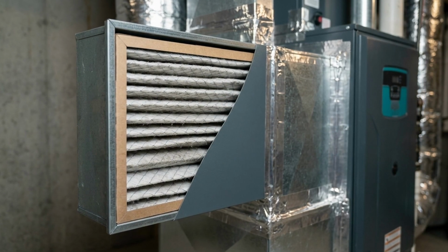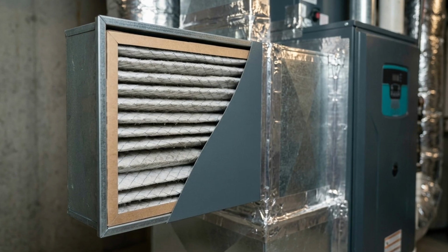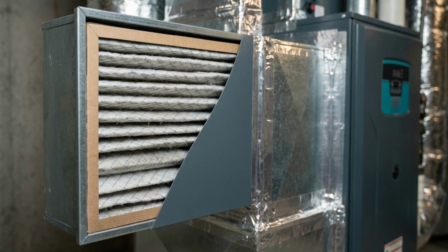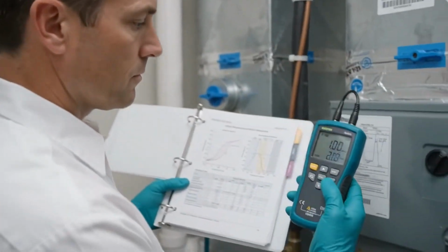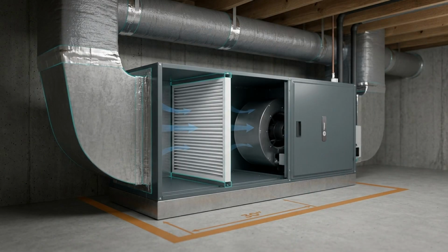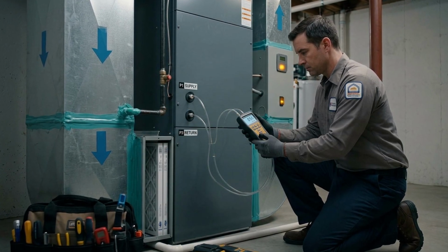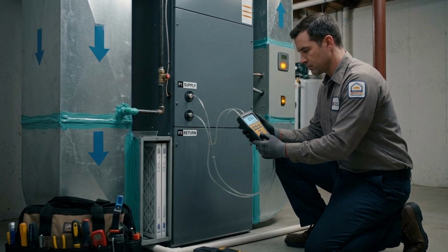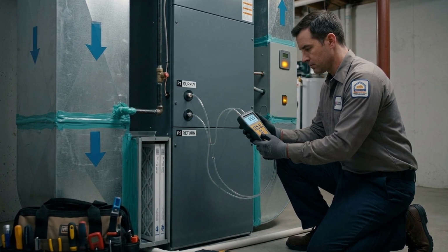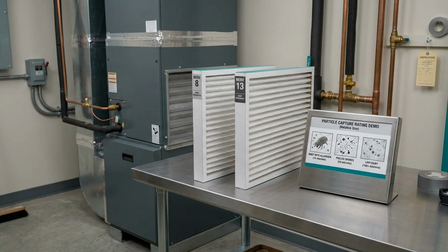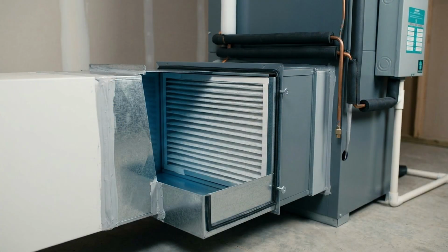If the comfort change persists, bring the filter model, dimensions, installation date, and observed pattern to a qualified HVAC professional. The professional can compare the equipment documentation with the filter's published performance and measure total external static pressure using appropriate test locations and procedures. That measurement can help separate filter resistance from a restrictive return, dirty coil, closed register, duct problem, or another system condition. The goal is not automatically to choose the lowest MERV number. It is to achieve the needed filtration without exceeding the pressure and airflow limits of the installed system.